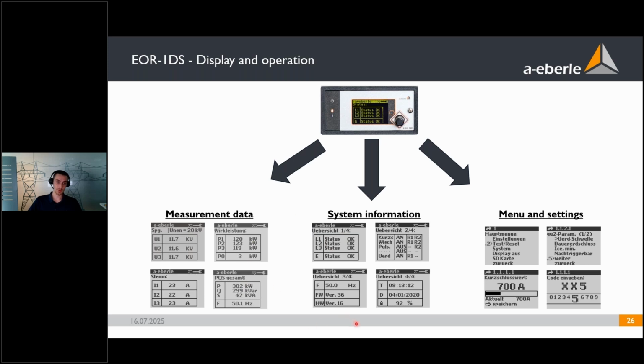Then also system information. So the status of each of the phases. Also which localization methods are in use and what are the relays that they indicate to. You have the overview of the set frequency. So not your measured frequency, but the frequency that you tell the device is the nominal frequency of the grid. Your firmware version and hardware version information. Also date, time, so a few system information pages.